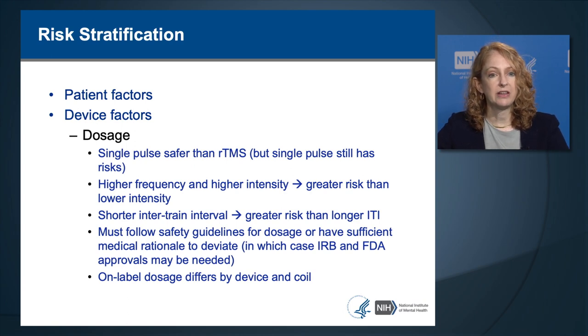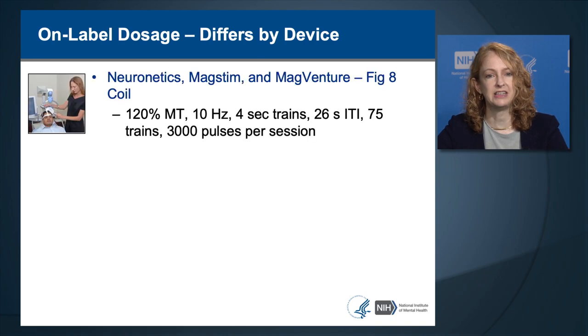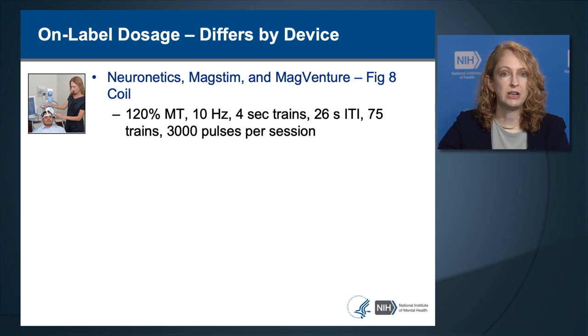On-label dosage differs by manufacturer. For figure-eight coils used by Neuronetics, Magstim, and MagVenture devices, the recommended on-label dosage is 120% of motor threshold, 4-second duration trains, with an inter-train interval of 26 seconds, giving 75 trains per session for 3,000 pulses per session. For the MagVita or MagVenture device using Theta Burst Stimulation, or TBS, the on-label dosage is 120% of motor threshold, giving bursts of 3 pulses at 50 hertz at 5 bursts per second, with 2-second trains, 8-second inter-train interval, and 20 trains for a total stimulation duration of 3 minutes and 9 seconds.